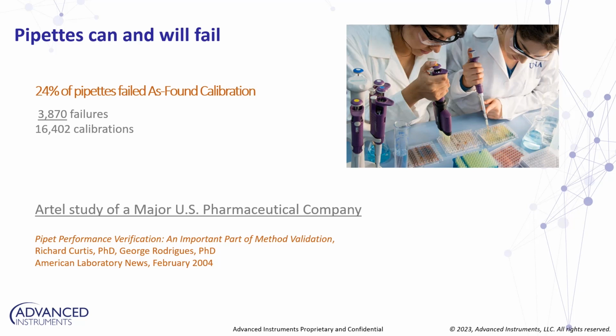Now, we performed a study on a Boston-based pharmaceutical company who over the course of 5 years experienced a 24% as found failure rate. Now imagine 1 out of every 4 pipettes was simply not functioning. For this company, their 24% failure rate was caused by 2 key items: variability in pipetting technique and the need to increase their pipette calibration and verification cycles.